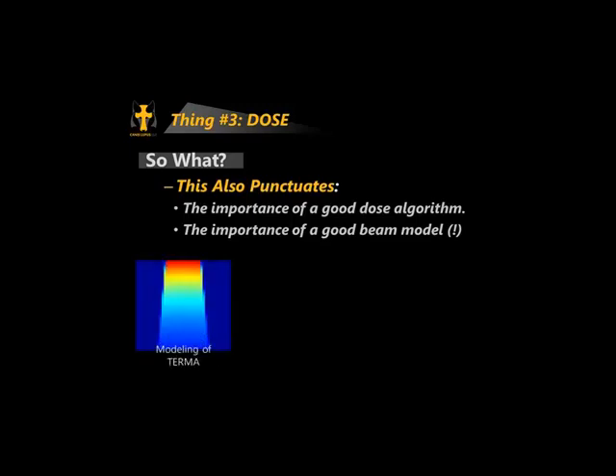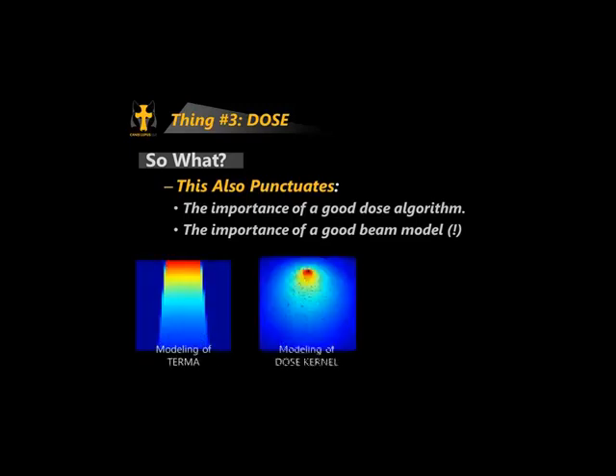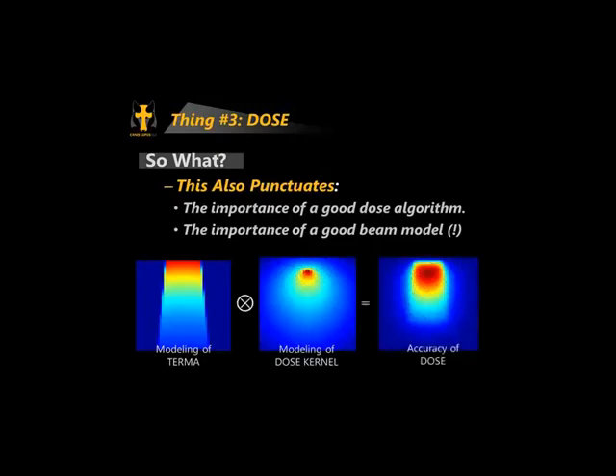You need to be able to see that blur and understand what's contributing dose at any point — its surroundings, its terma, its dose kernels. This also punctuates the importance of a good dose algorithm and a good beam model. A good beam model needs to accurately model terma and dose kernels in order to model dose accurately, and there are different hoops to jump through depending on your planning system.